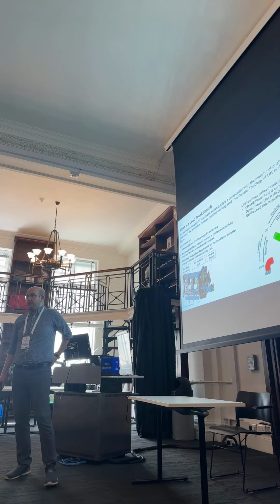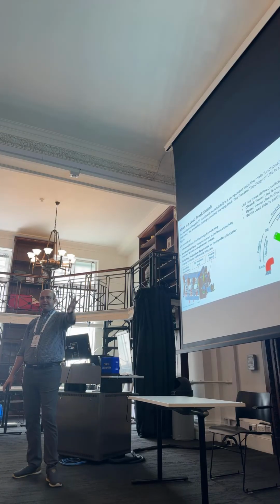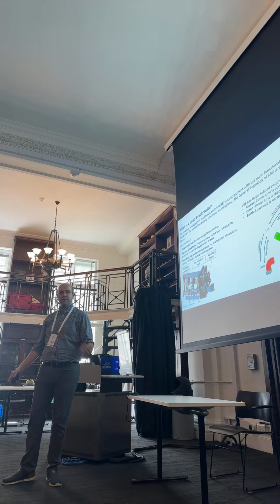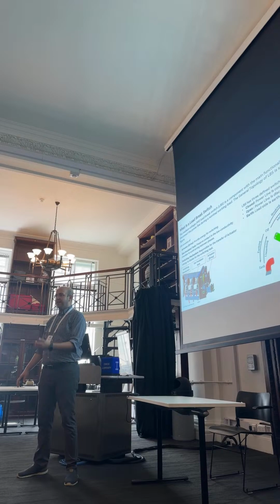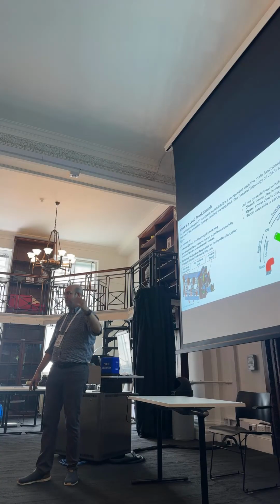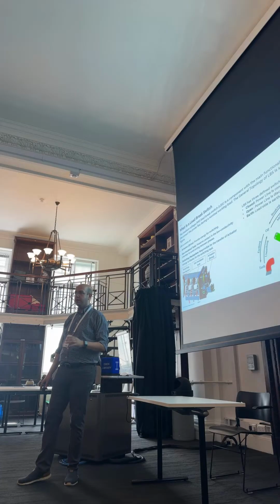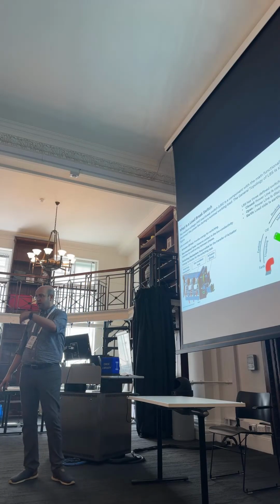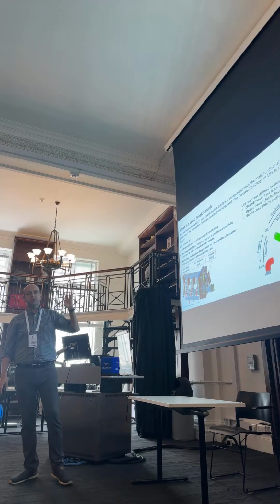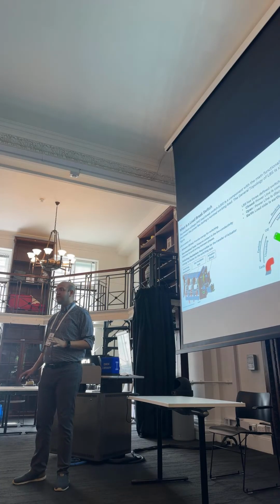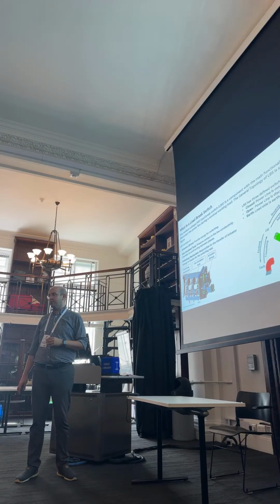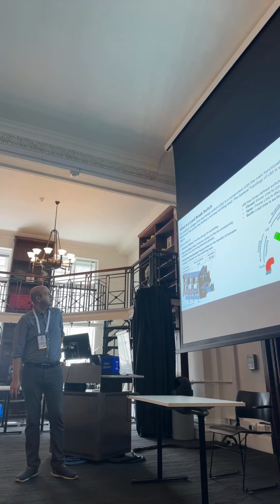First of all, what is the load break switch? You're all familiar with the light switch at home, which disconnects the line or electricity. Now imagine a city that needs to block or stop electricity for part of the city, a factory, or a power plant like a solar plant that needs to turn off at night and disconnect from the system. In a medium voltage load break switch, in the range of 12 to 36 kilovolts, you need devices that can connect and disconnect the line safely. That's where the load break switch comes into play.